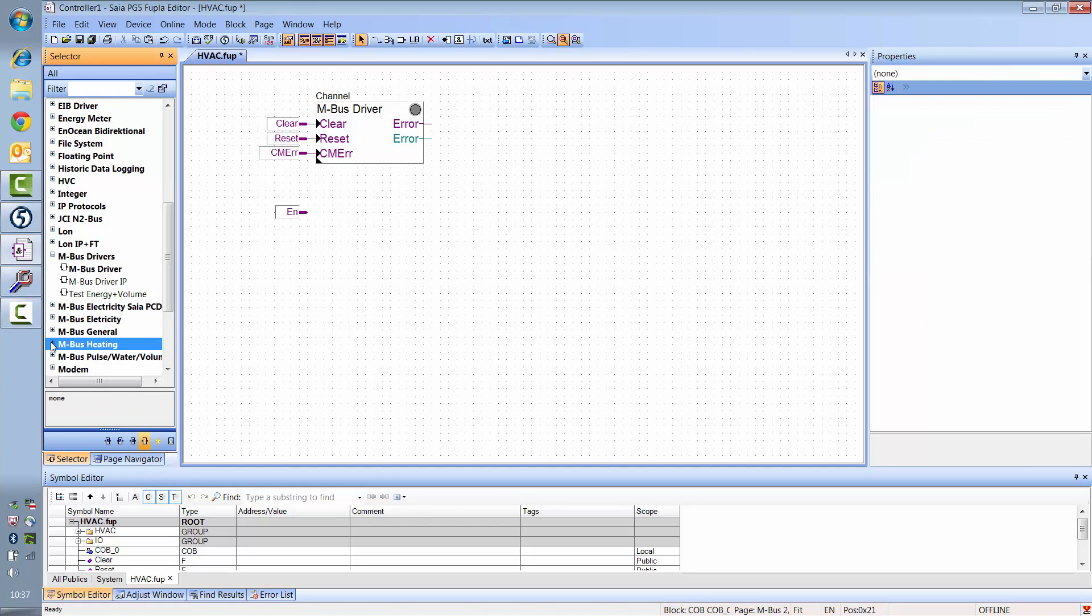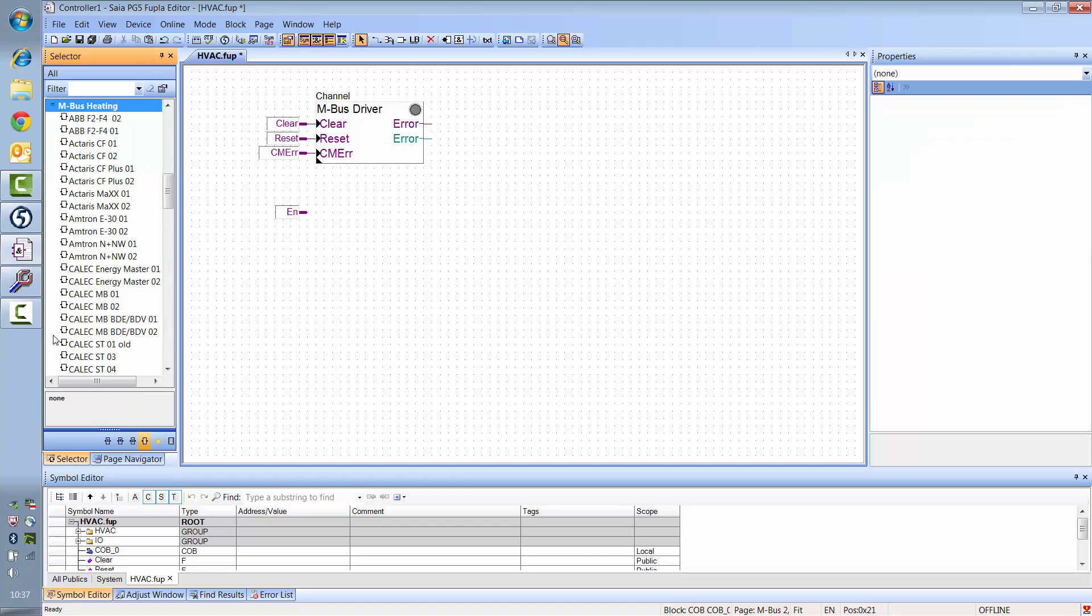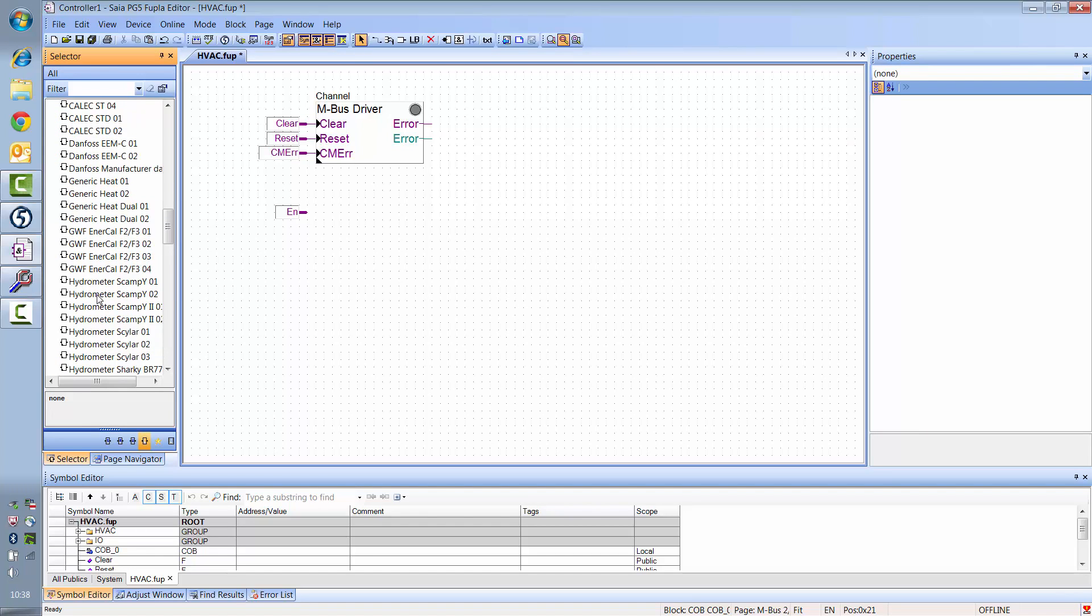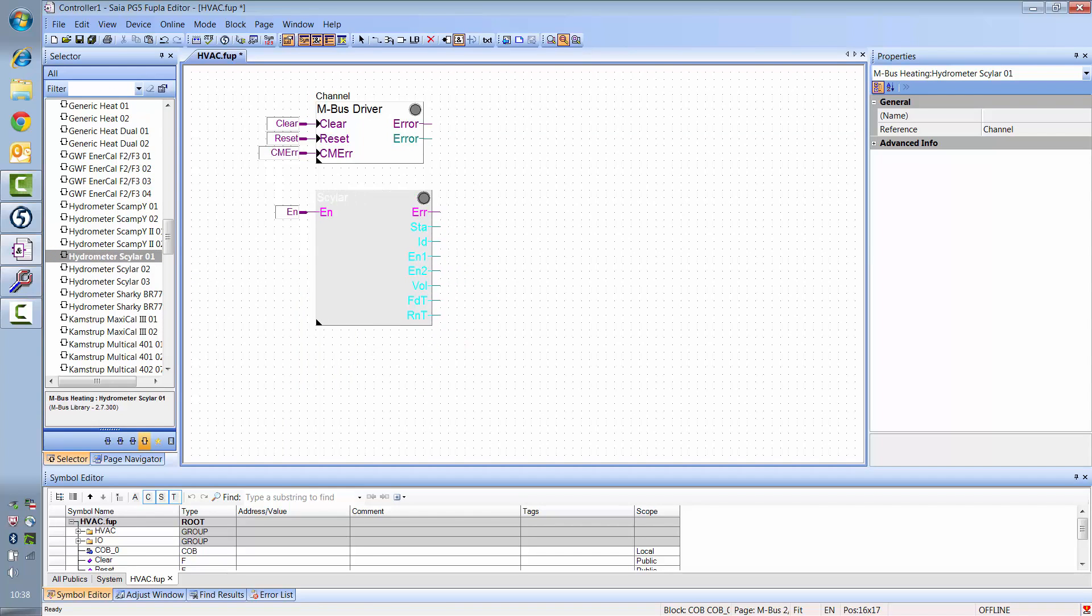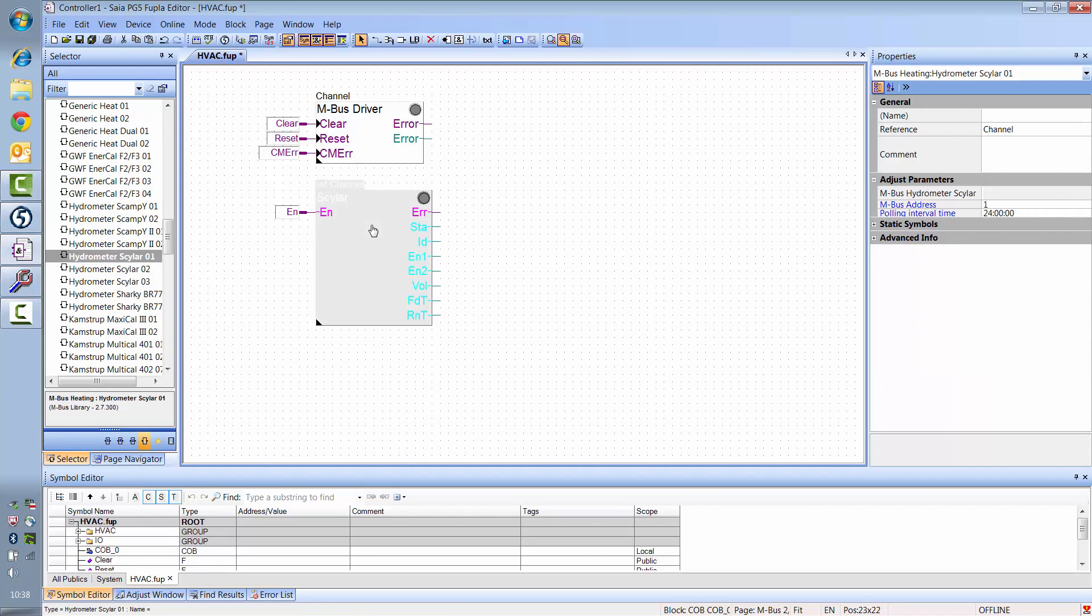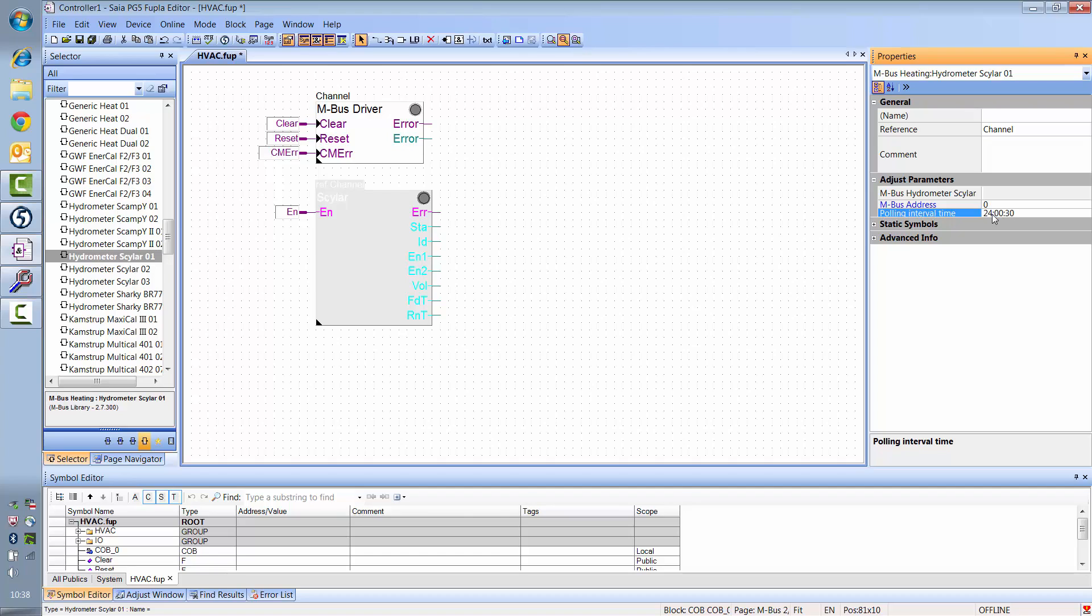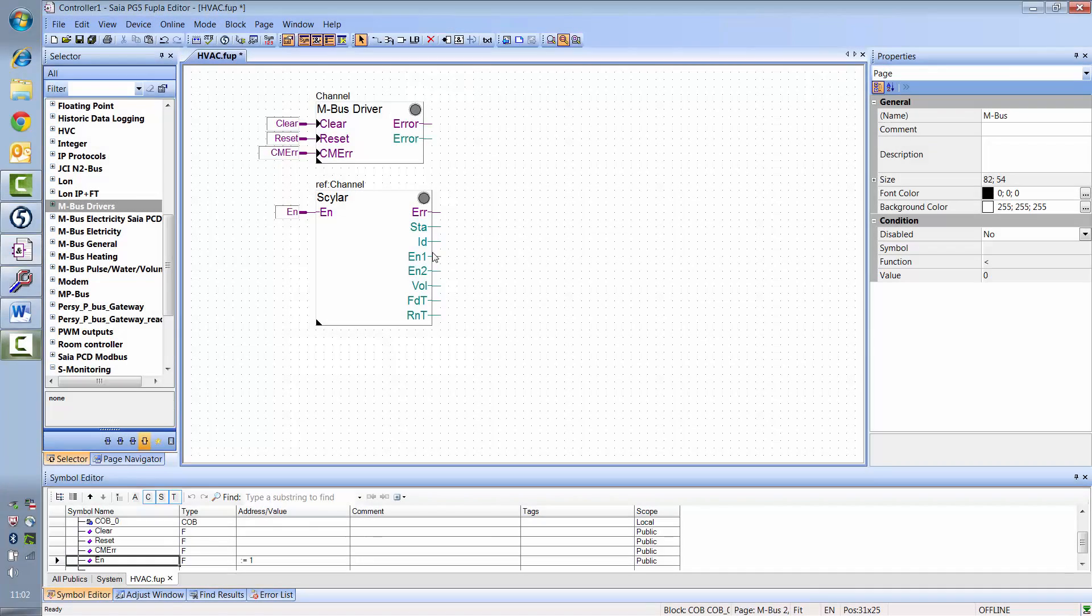Now we still have to set up the communication F-box. For most meter types, there's already an F-box available. In my case, it's a Hydrometer Scylar. All that has to be set here is the M-Bus address and the data polling interval. I'd like to read data every 30 seconds. Now we'd like to feed the M-Bus energy meters values into the S-Monitoring application.